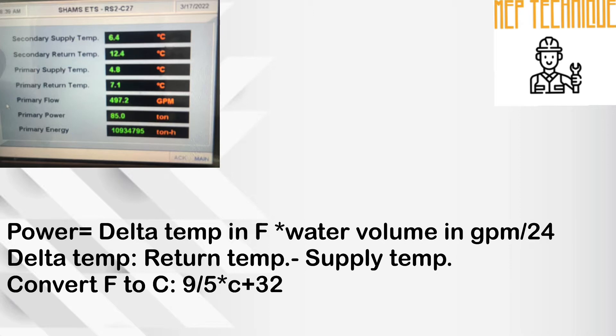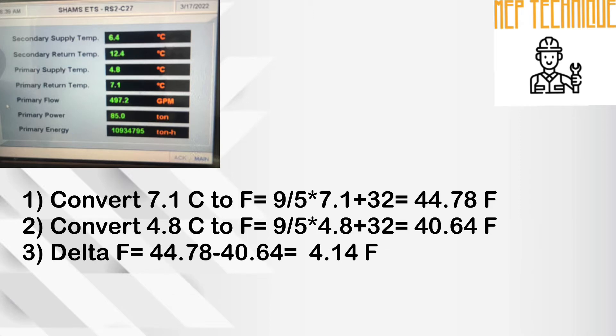So we will apply this formula to calculate our load. We convert 7.1 degree Celsius to Fahrenheit and the value is 44.78 degree Fahrenheit. Similarly, 4.8 degree Celsius converts to 40.64 degree Fahrenheit. And the delta temperature is 4.14 degree Fahrenheit.